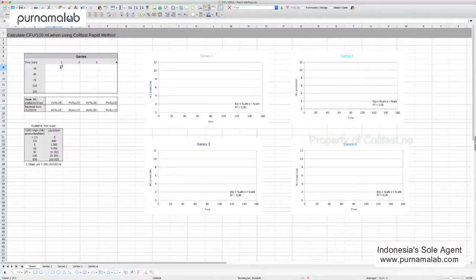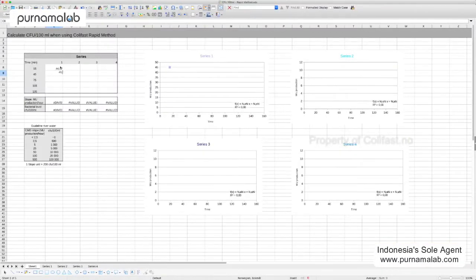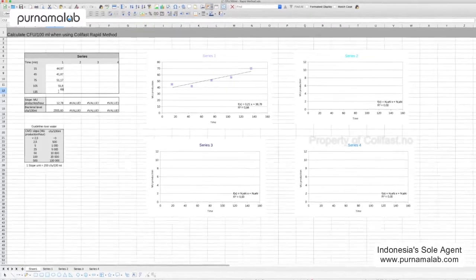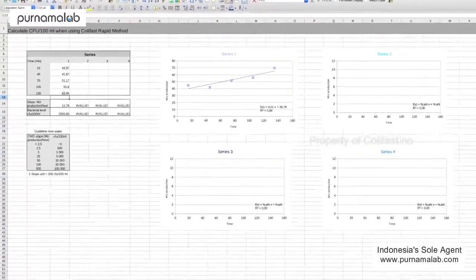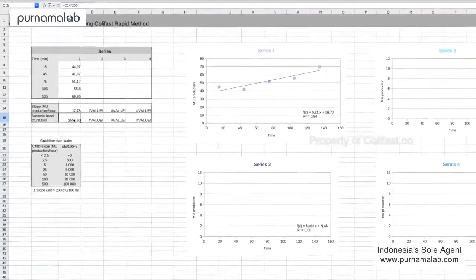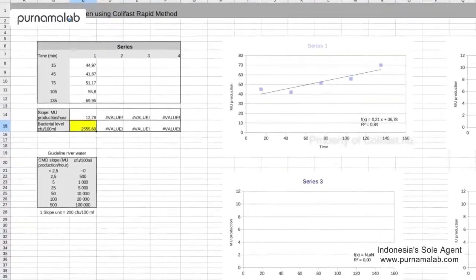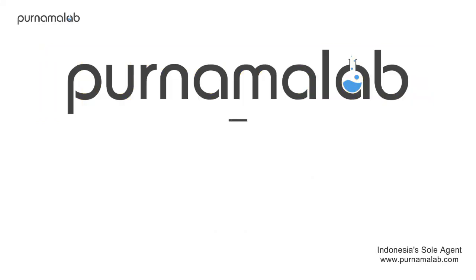Filling in the data from the measurements in this Colifast spreadsheet template, we are now able to plot all the points, calculate the best fitting line, and get the slope of that line. This slope number can be used to approximate a number for the bacterial count in CFU, colony forming units, per 100 milliliters. This final bacterial count value can be seen in this yellow cell. The water measured contained an estimated value of 2,555 cells per 100 milliliters.